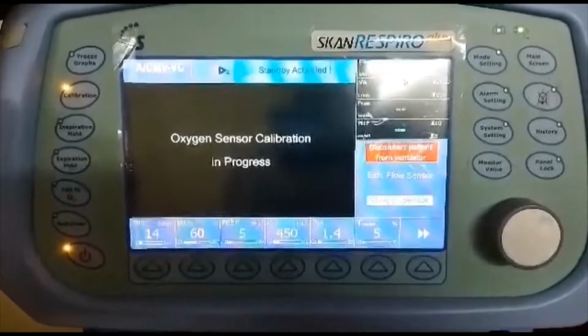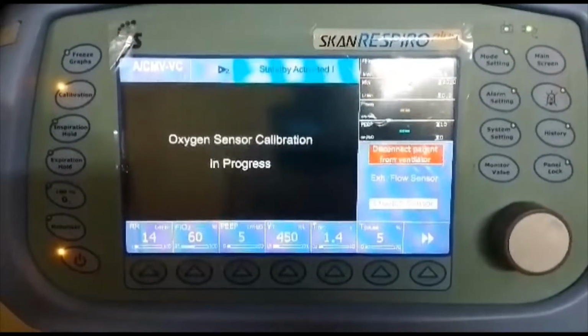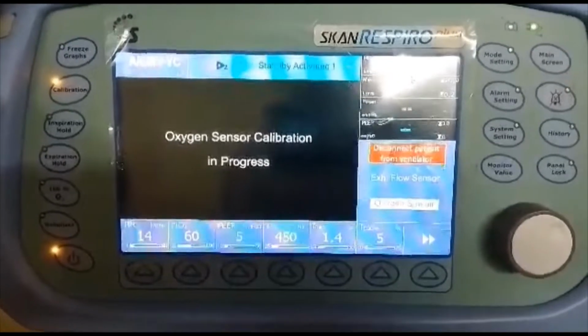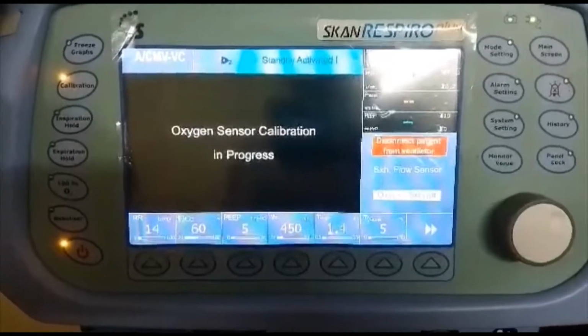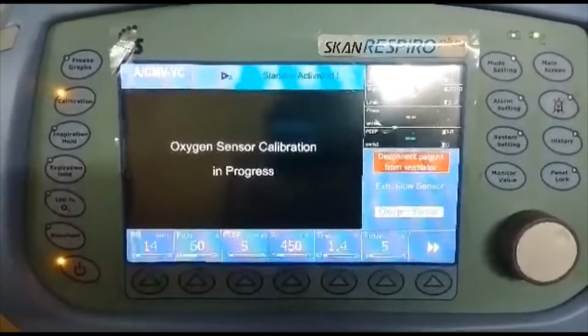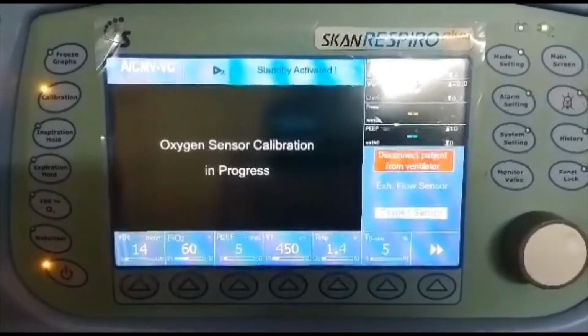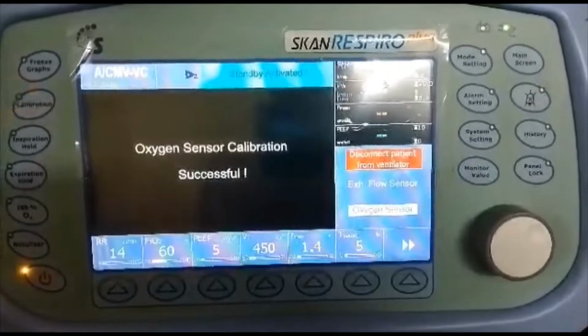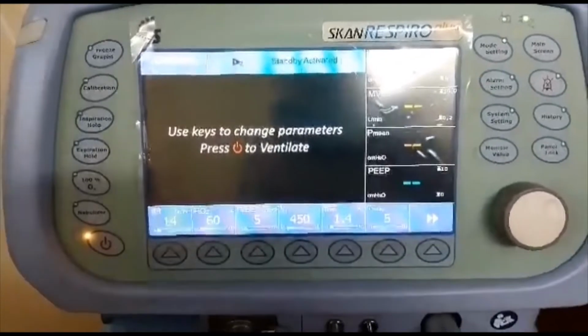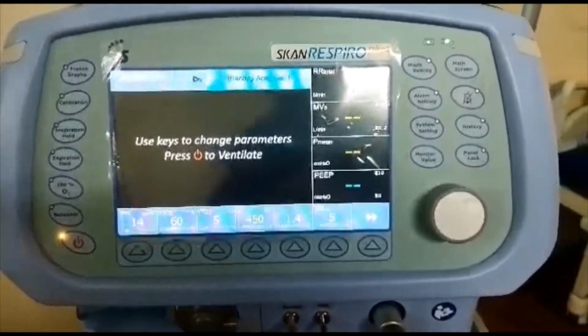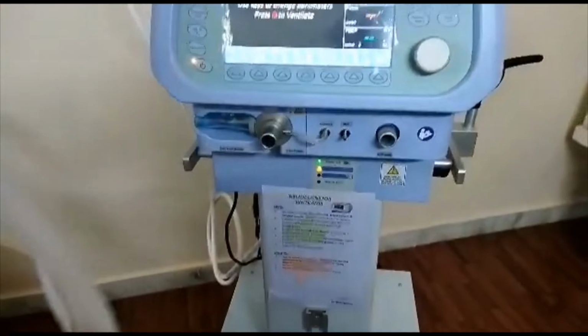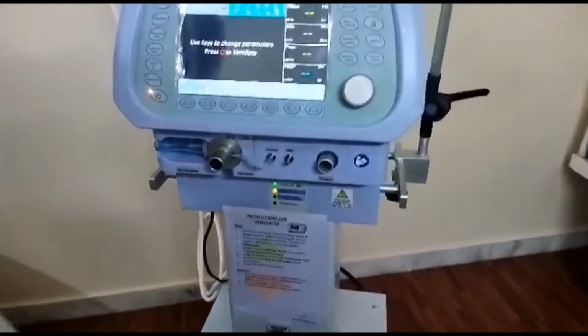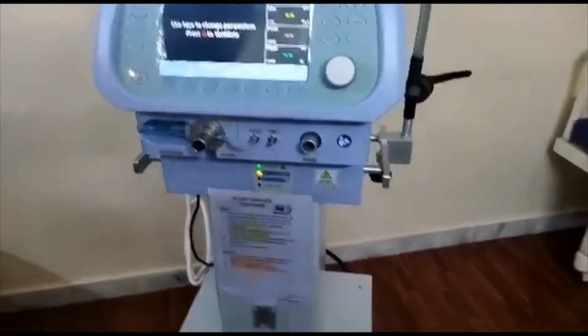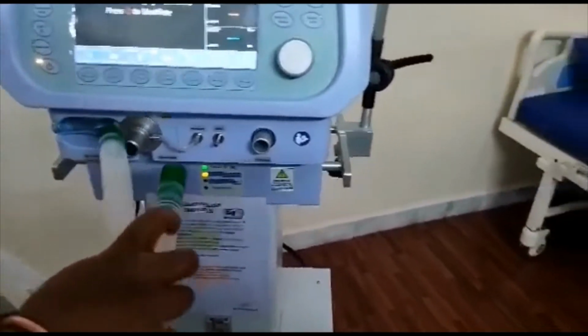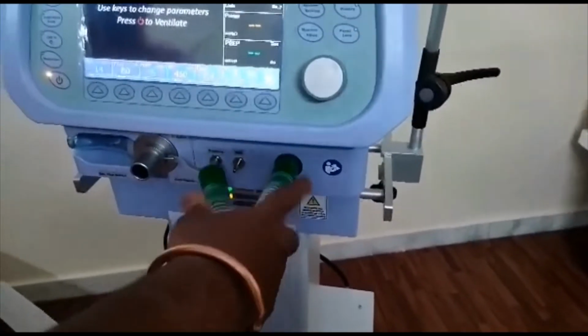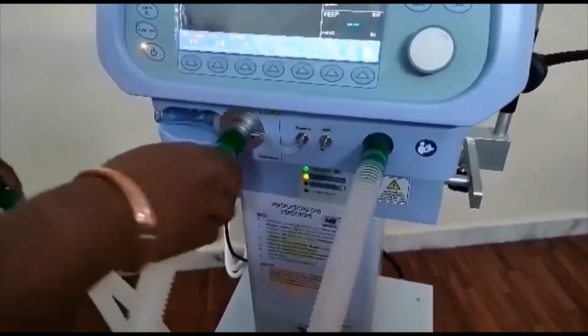The oxygen sensor calibration will take a few minutes. So 1 minute to 90 seconds it may take. So wait till the calibration self-test passes. Successful. Now we'll connect the patient circuit with a test lung. So first we have to connect to the inlet, then the respiratory outlet.